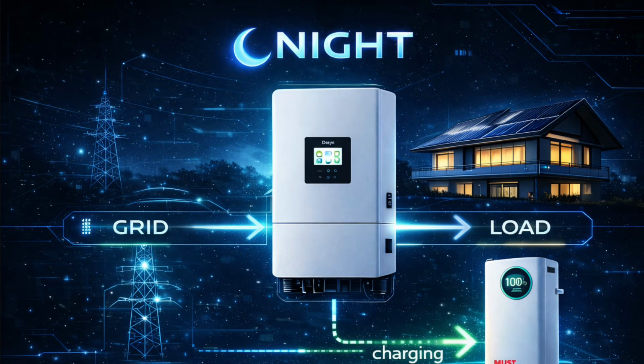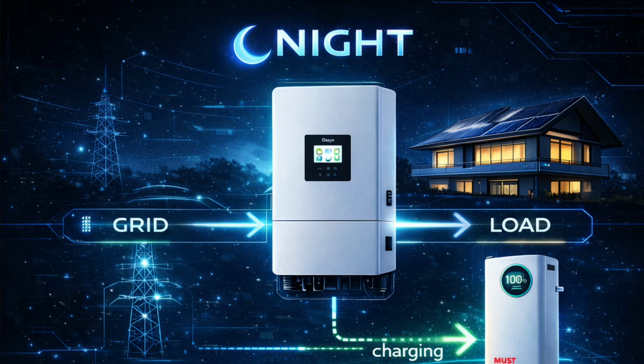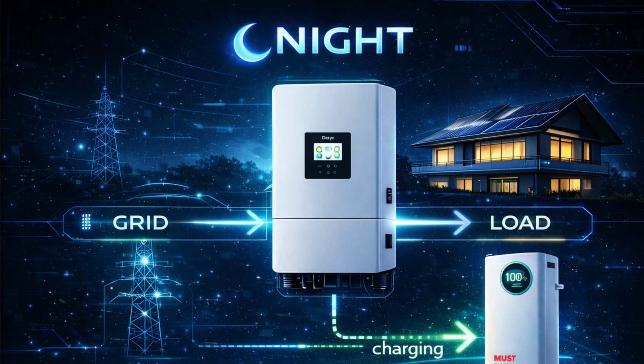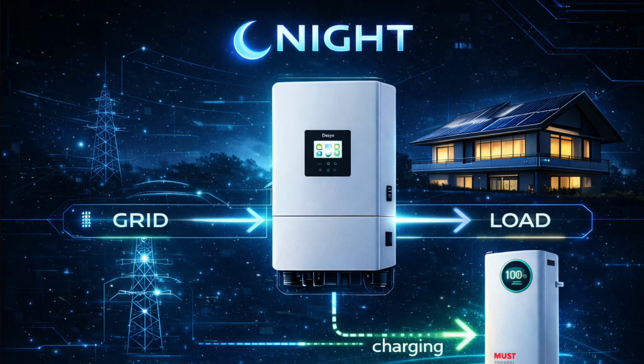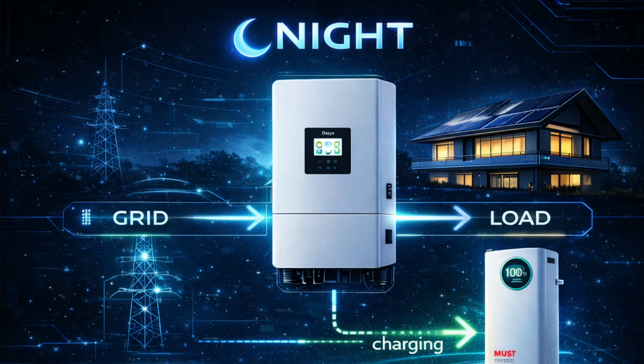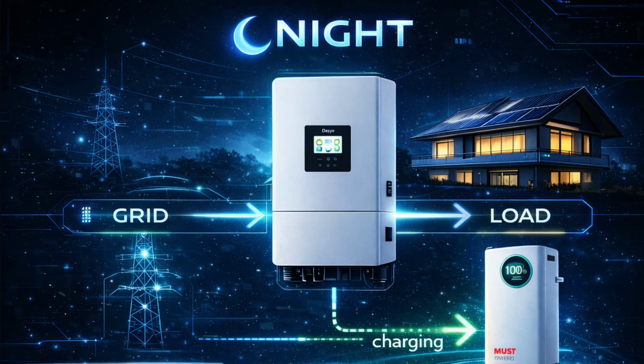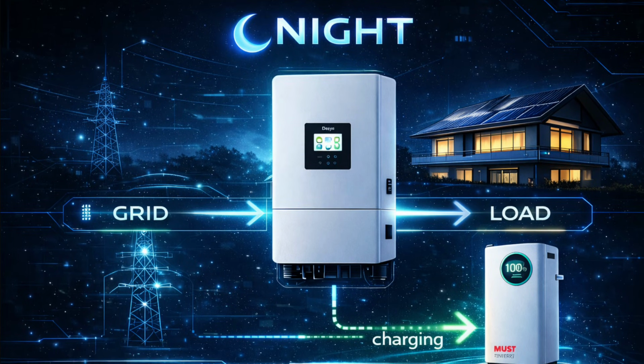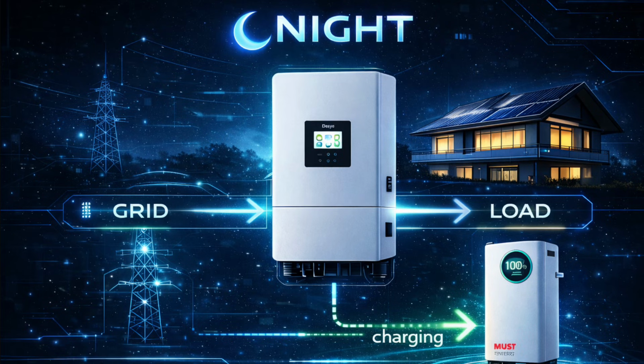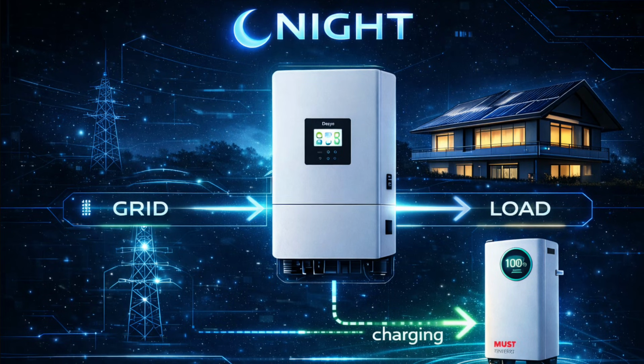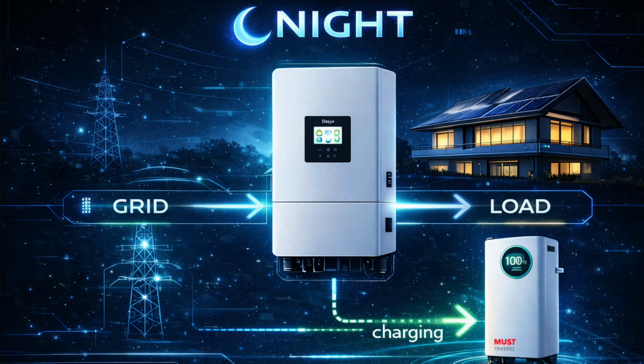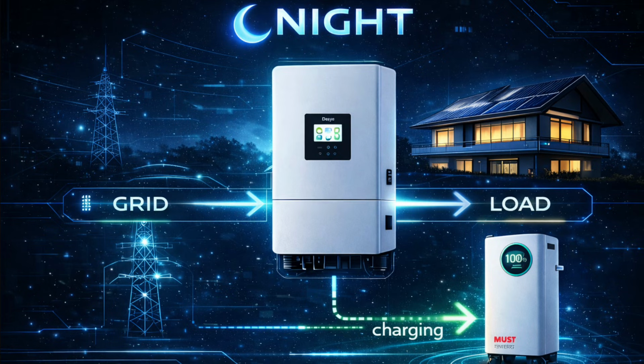Night mode. It operates during the period when the night tariff is active. In my case, the electricity price during this time is 50% of the daytime rate. The load is powered through the inverter but directly from the city grid, and the battery is charging if necessary. During the period when the night tariff is active, there is only one operating mode. All the others are daytime modes.